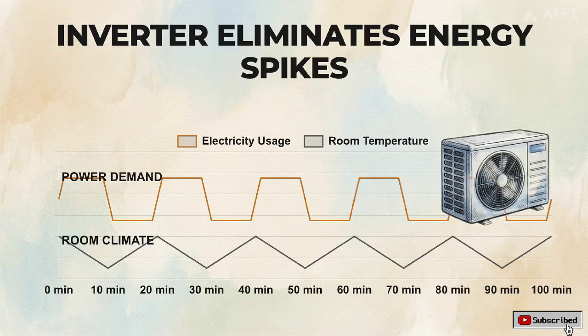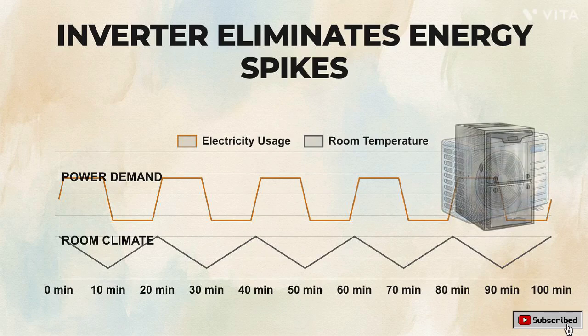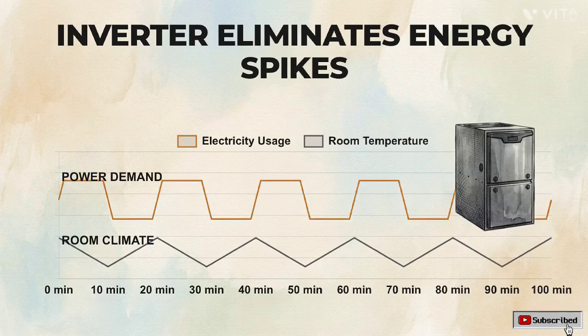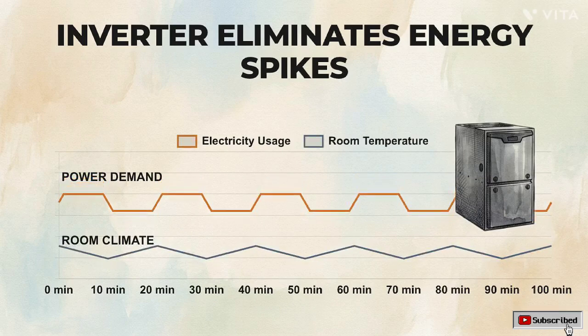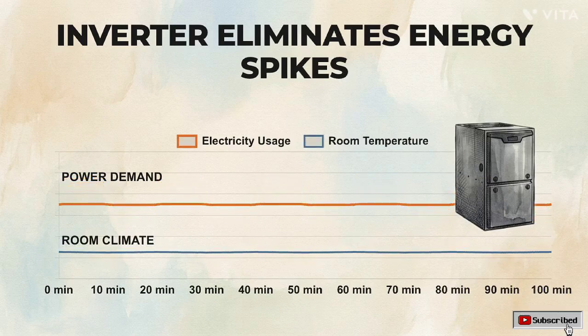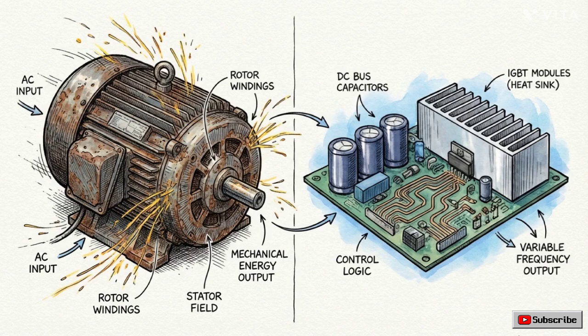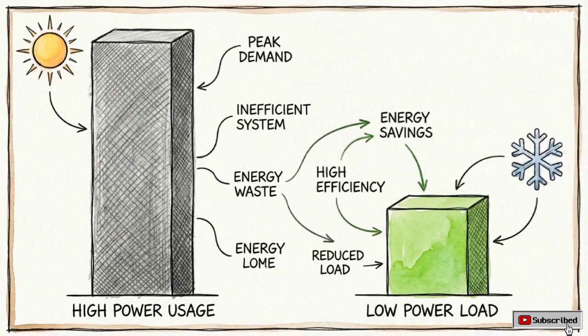The modern alternative is an inverter compressor powered by a variable frequency drive. Instead of stopping and starting, an inverter dynamically scales its speed to match the room's exact cooling load. As you see on the graph, the waveform stabilizes, keeping room temperature completely flat. Running continuously at a low speed uses far less power than constantly starting a heavy motor. This specific mechanical difference delivers up to 44% in annual energy savings.